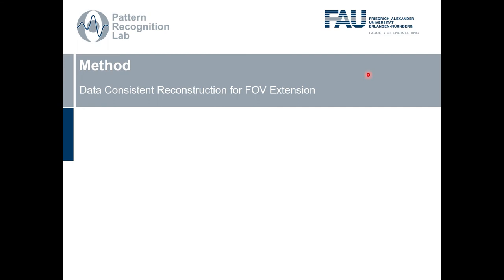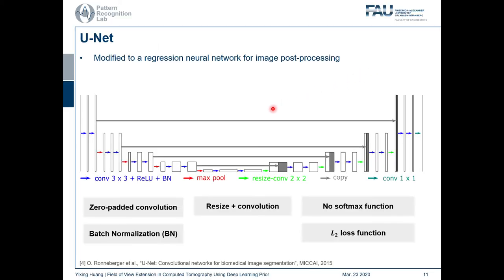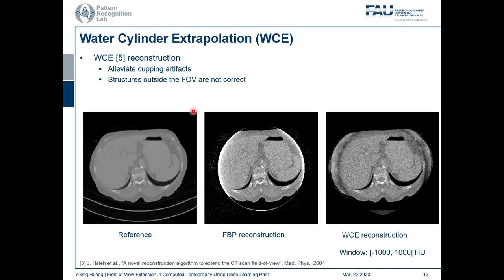Here I will talk about our data consistent reconstruction method for FOV extension. The neural network we use is the state-of-the-art U-Net. The input of the U-Net is an image reconstructed from water cylinder extrapolated (WCE) data. Water cylinder extrapolation is a widely used extrapolation method to reduce cupping artifacts. Compared with the FBP reconstruction, the brightness or cupping artifacts are reduced very well. However, the anatomical structures outside the FOV are still not correct compared with the reference image, which is why we still need deep learning to further improve these anatomical structures outside the FOV.